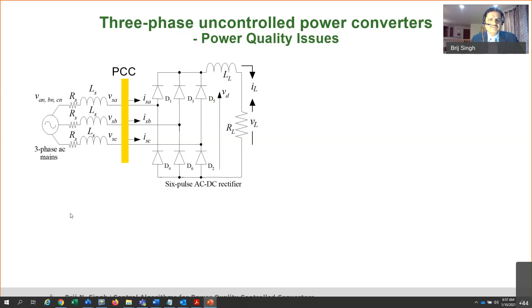So the idea is that IEEE came up with a standard called IEEE 519. As per that, you must be compliant with a certain amount of harmonics in voltage and current at PCC. So if you connect your load, you have to be responsible for your load if it is generating harmonics. And same thing in the RC load. So in the RL fed load, harmonic is roughly 30 to 34%. It can produce distortion in the voltage. And in the RC load, the current is even peakier in nature, so it gives even higher than that, 50%. So those loads are called nonlinear loads.